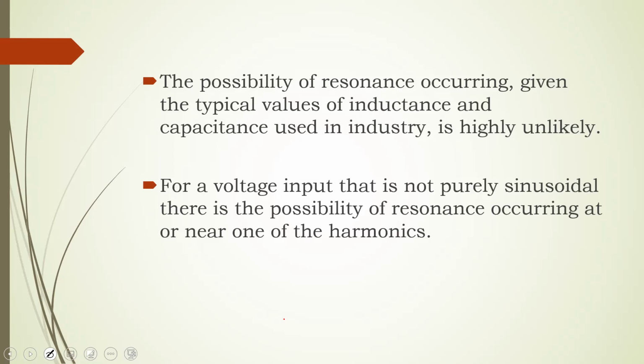When I have a pure sinusoid, I mean, you know, we operate at 50 hertz. Nice sine wave. Given the values of inductance and capacitance that you will come across in the industry, you're not likely going to see resonance occurring. However, when we're dealing with non-sinusoidals, yes? Or in other words, when we're dealing with complex waves, and these, by the way, students, do occur in industry, yes? The possibility of resonance occurring at one of these harmonics is then increased. So it may not resonate at 50 hertz, but it may resonate at 150.